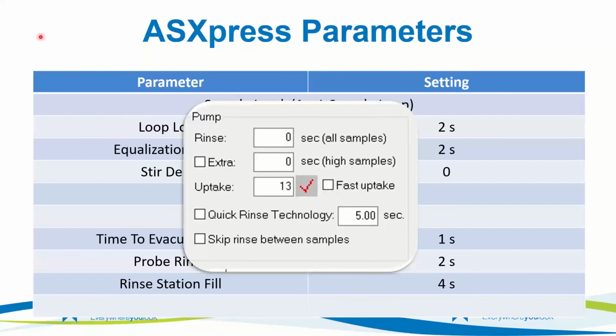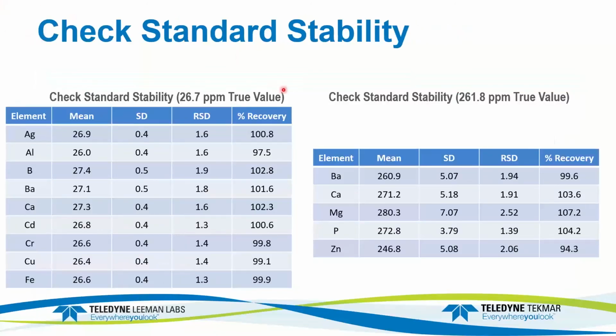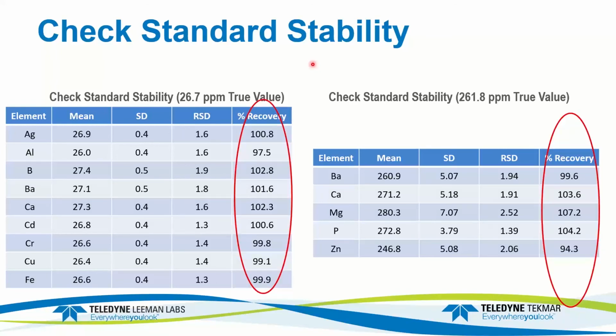So we found that in this case, with this setting, the pump speed at 13 seconds was enough to be able to get everything done, so that when we started running samples, the sample in the spray chamber had been equilibrated and everything was ready to roll. Okay. So again, we did the check with the certified standards. I won't present that data again because it was pretty much the same, but even the check standard data stability, again, was comparable to what we had earlier. Again, there were no check standard failures.